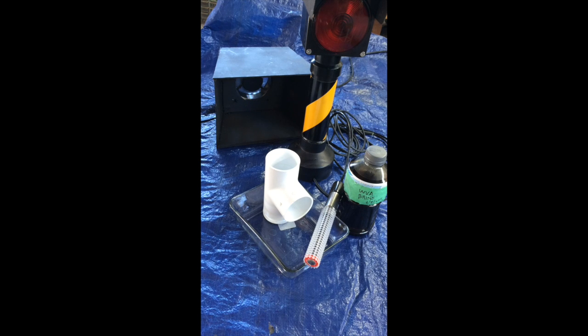It is 11:10 a.m. on the 6th of November. The lab temperature is 62 degrees, and this is a test and demonstration to see if the TRM sensors SensorCom combo probe can detect West Virginia brine. The brine has been received yesterday. It's dark and has a fairly strong odor of hydrogen sulfide. The fume extraction system in the background is basically just there to keep the concentration of hydrogen sulfide fumes down.